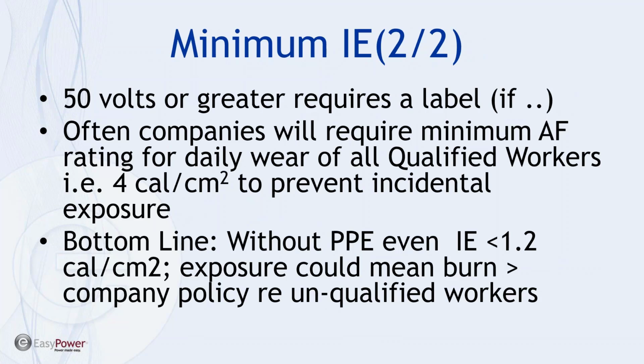If any panel that needs to be worked on is greater than 50 volts, then it requires a label, again, if the operator needs to do it while it's energized and exposes human activity. Often companies will require a minimum rating on qualified workers, for instance 4 calories per square centimeter, to prevent incidental exposure. And so on our one-line diagram, we may want to indicate and highlight any bus that has greater than 4 calorie exposure, which again is a company policy dictate. It's not required by NFPA 70E.